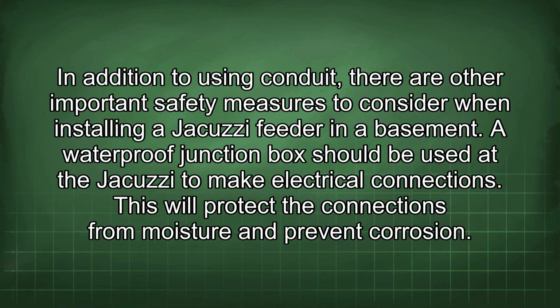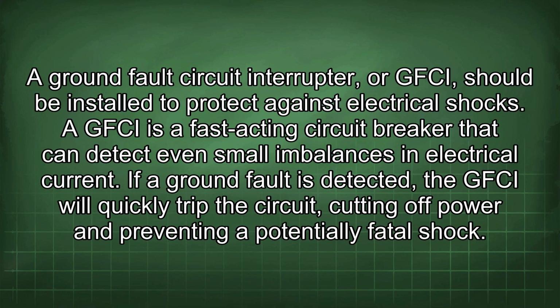In addition to using conduit, there are other important safety measures to consider when installing a jacuzzi feeder in a basement. A waterproof junction box should be used at the jacuzzi to make electrical connections. This will protect the connections from moisture and prevent corrosion. A ground fault circuit interrupter, or GFCI, should be installed to protect against electrical shocks. A GFCI is a fast-acting circuit breaker that can detect even small imbalances in electrical current. If a ground fault is detected, the GFCI will quickly trip the circuit, cutting off power and preventing a potentially fatal shock.